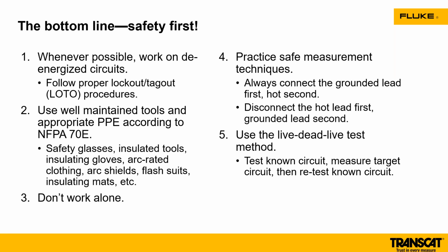Depending on what type of meter you're working with, you may have voltage running through. I actually heard a story of a guy who had put his red test lead on voltage first. He was about ready to put his black one on, and he got an itch on his nose. He went to rub it with the black test lead in his hand, and it seared his cheek because the meter he was working with didn't have enough internal impedance, and it basically gave him a scar for life. So good practice is always going black on, then red on, red off, black off. And always use that live, dead, live test. Make sure that that meter's working correctly.